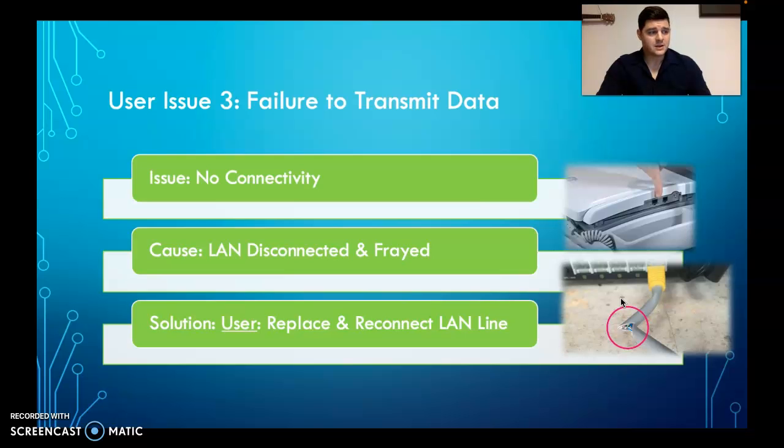As far as mitigating future issues, just giving the clinician and user a rundown on what connections are being used with the Muse system, and what cords and cables and what external parts go into that unit. So what needs to be plugged in, where it needs to be plugged in. You can give them a sticky note if you need to, and put it on the back of the machine, like a simple checklist. Here are the things that you need to make sure are plugged in to this machine in order for it to operate properly.